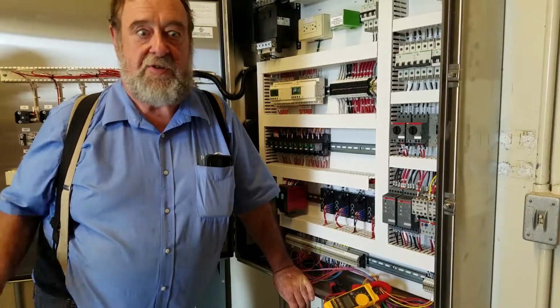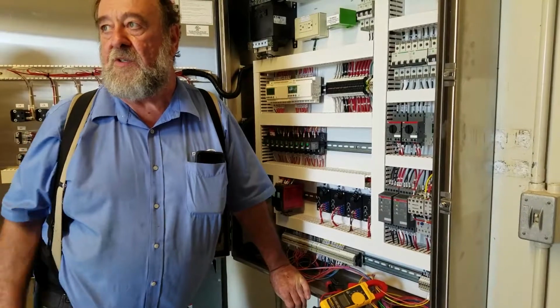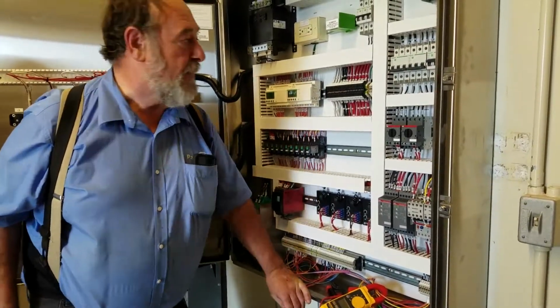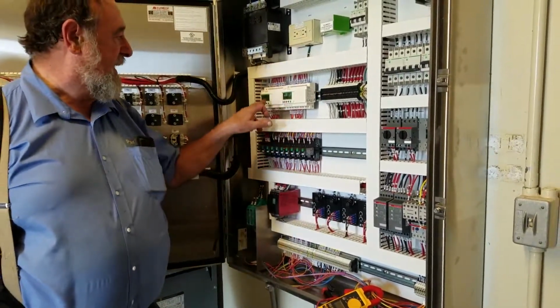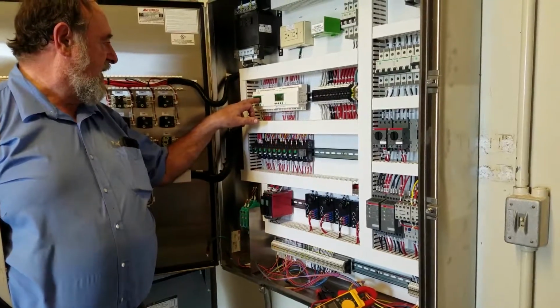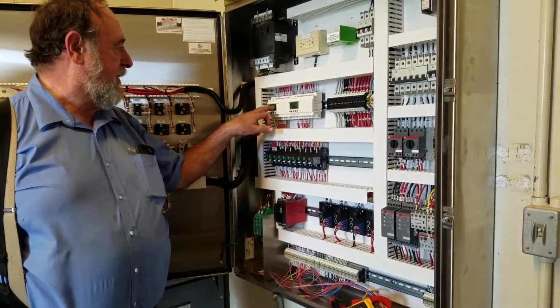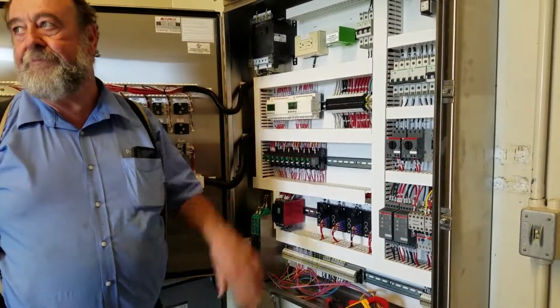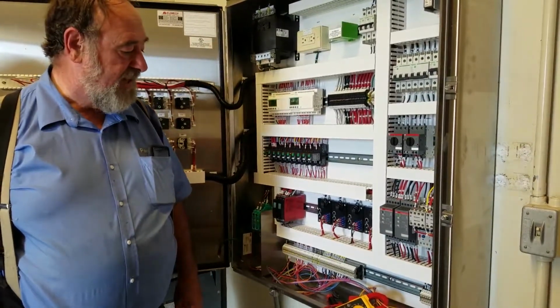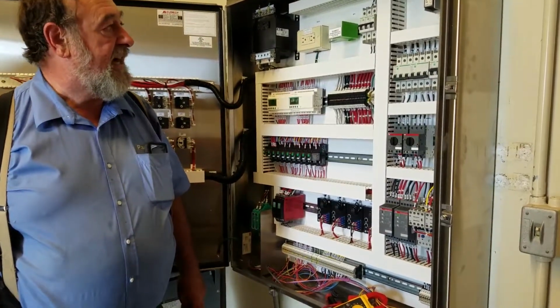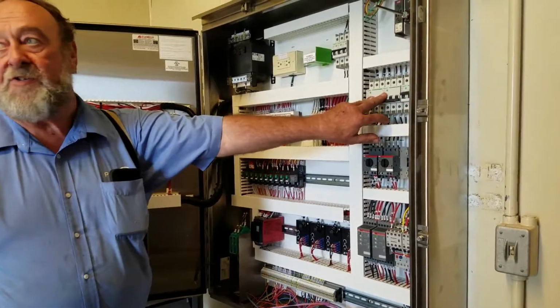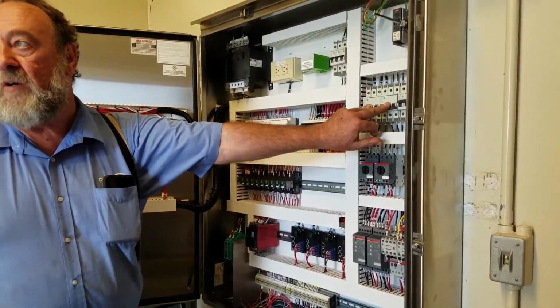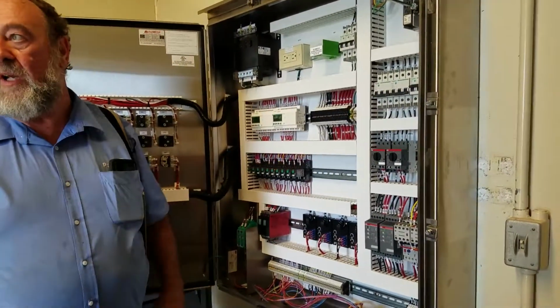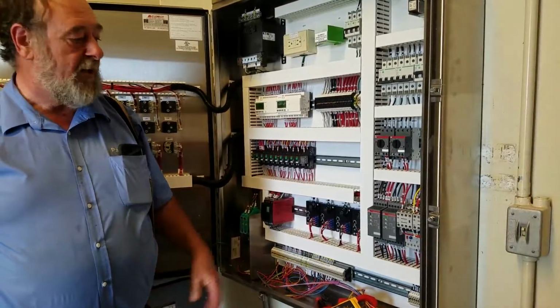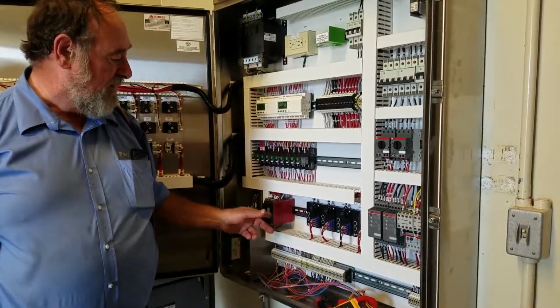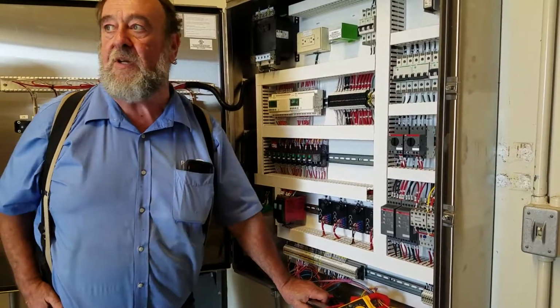Again, if it fails, the screen will just run and run and run because it's not doing it. But I know it's getting a process signal because I hear the relay clicking and I can see the key light flash on and off up here. So it's not messing up. I guess the next thing we're going to do, these are circuit breakers for the press and conveyor. We can walk around the running screen, and then I'm going to break off and get a hold of the panel builder and find out which parameters are messed up inside there.